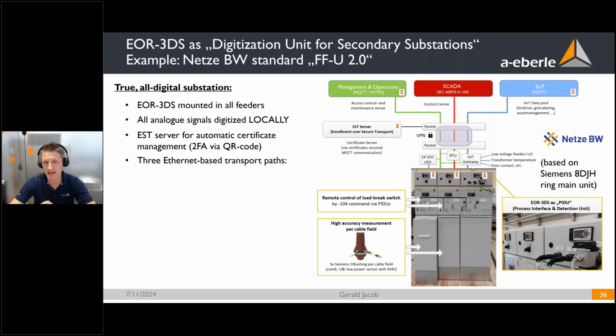Every cable field has a motor control unit, so the switching operation is done in a way that the command comes from SCADA, goes via the RTU to the EOR3DS. The EOR3DS compares everything, does the security features, and in the end, if everything is okay, sends the command via relays to the motor control unit, and the motor control unit switches the load breaking switch in or out.